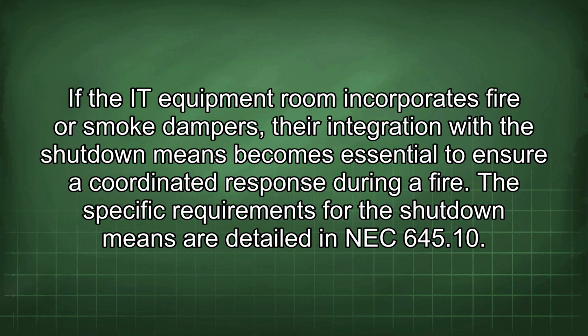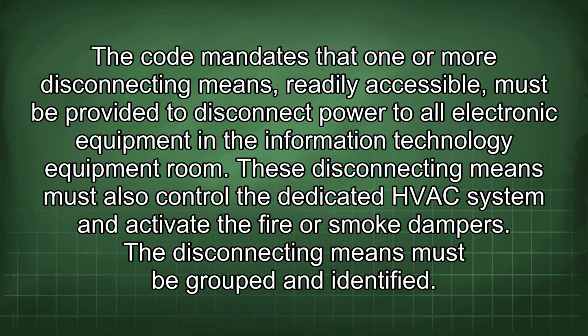The specific requirements for the shutdown means are detailed in NEC 645.10. The code mandates that one or more disconnecting means, readily accessible, must be provided to disconnect power to all electronic equipment in the information technology equipment room. These disconnecting means must also control the dedicated HVAC system and activate the fire or smoke dampers.